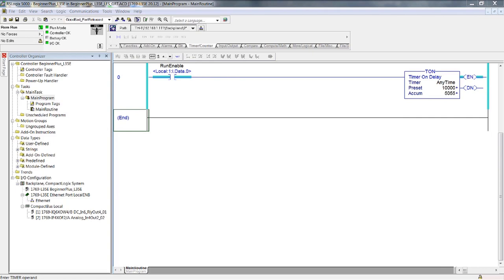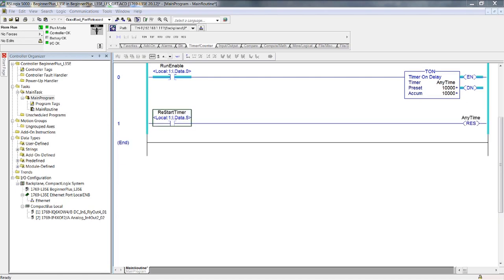On my digital field device simulator I just pushed the push button momentarily to get the change of state. That's the advantage of having at least one input that can be maintained on, maintained off, or normally open or normally closed. I then had you add a second rung — simply an input on your digital field device simulator — so you can push the button to reset the timer and it starts over. The timer timing bit tells us whether the TON has been enabled. Now we're going to use the comparison instructions as an analysis tool.